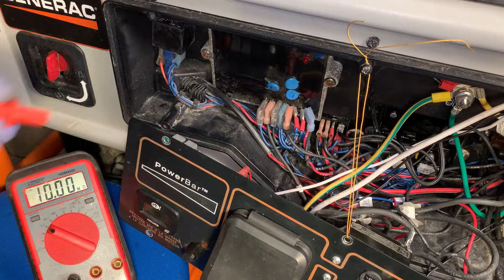I want to check the wires going to the brushes first. These two here go to the brushes—actually the blue wires go directly to the brushes, this one is just a ground. If I connect one lead to the blue and another to ground, I should see close to 8 ohms, which is what we get testing directly on the brushes.